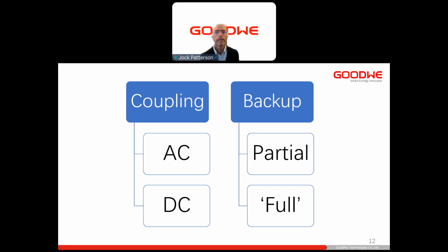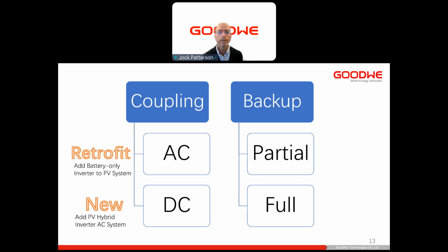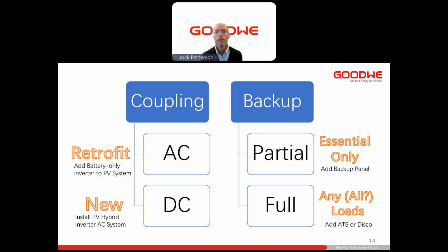In any backup scenario, we can describe at a high level whether it's using AC or DC coupling, and whether it's partial or full backup, and we'll look at combinations of these. Other terminology: AC coupling is often referred to as retrofit, because it applies when we retrofit an existing PV system by adding battery, and DC coupling is a new install, just a PV hybrid inverter with storage. Partial backup is often referred to as essential loads, and you need to add a backup panel, whereas full backup is all loads, which requires a disconnect method from the grid.